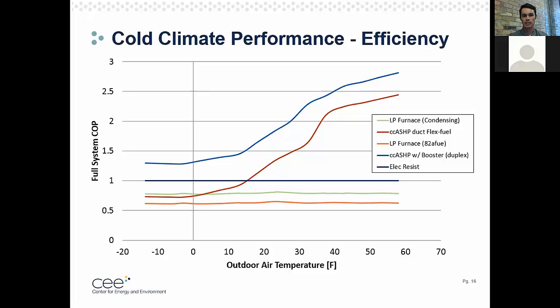And that happened at different temperatures depending on the time of the year and the weather. But as you can see, at about 13 degrees, you're always switching over and operating with just that propane furnace to meet that load. So with this system, it's a steeper drop off because it's a hard switch over between when your heat pump's operating and when your furnace is operating, and they both aren't ever operating at the same time.